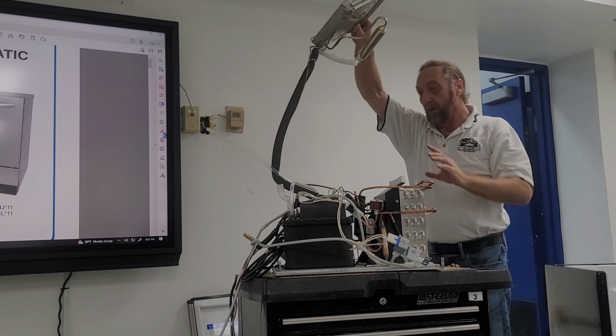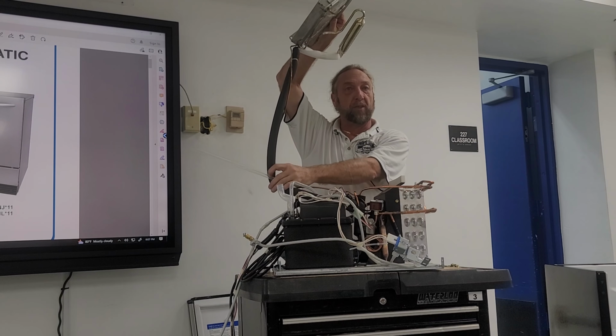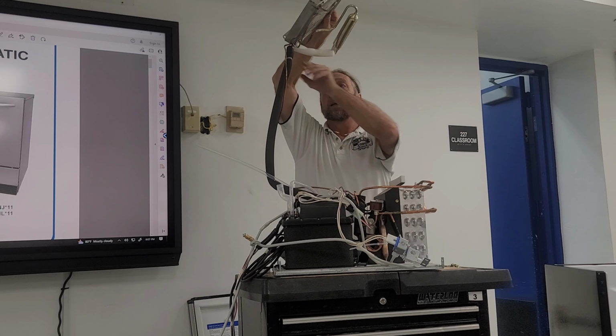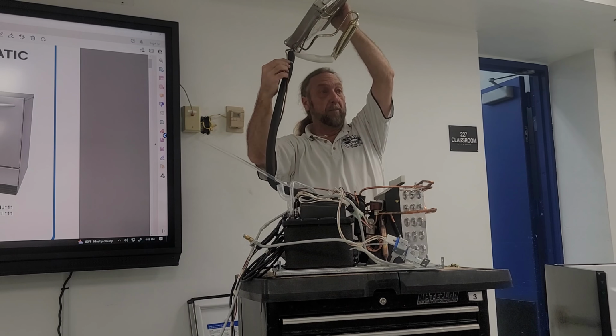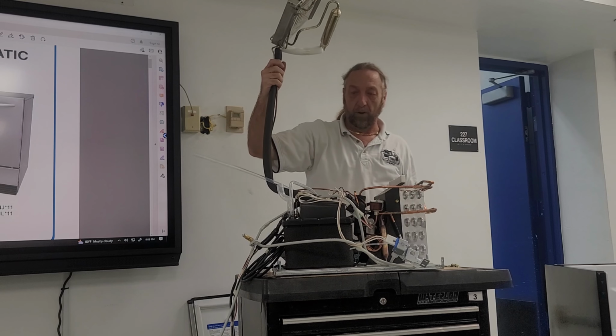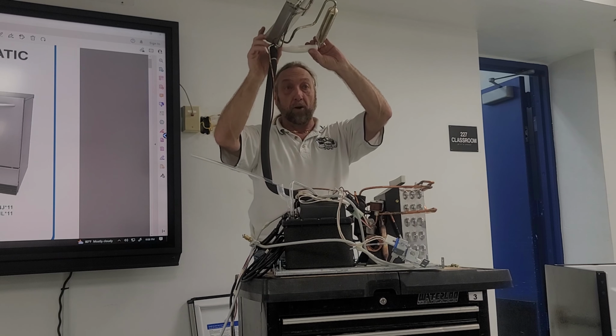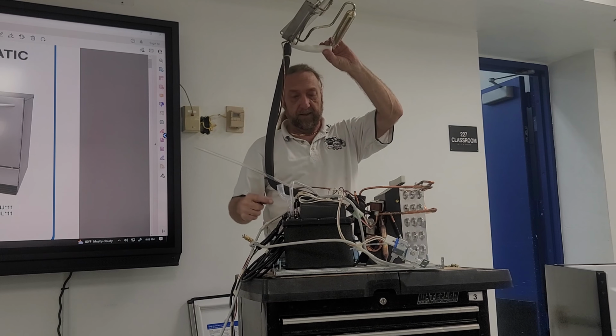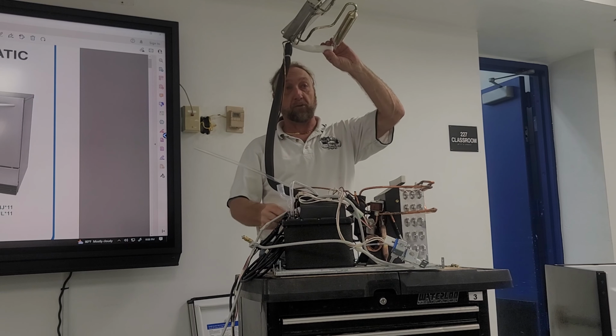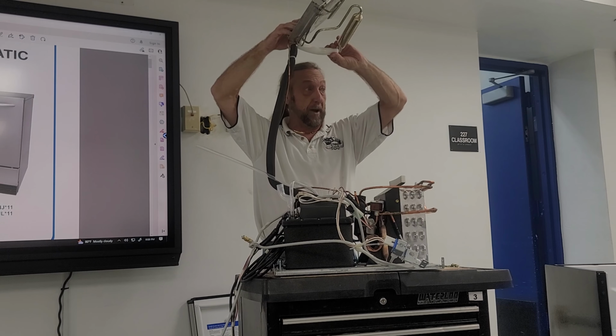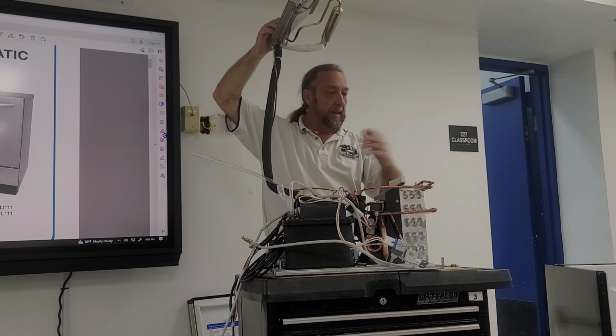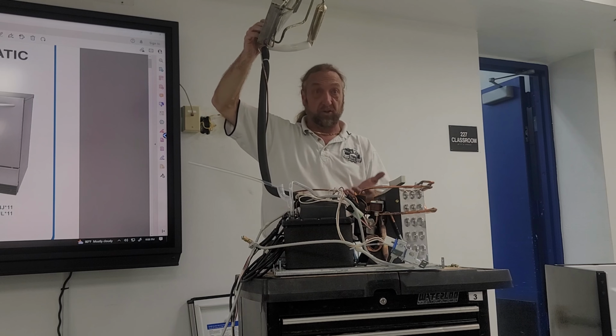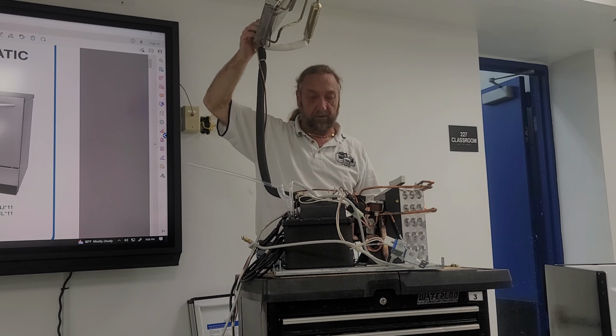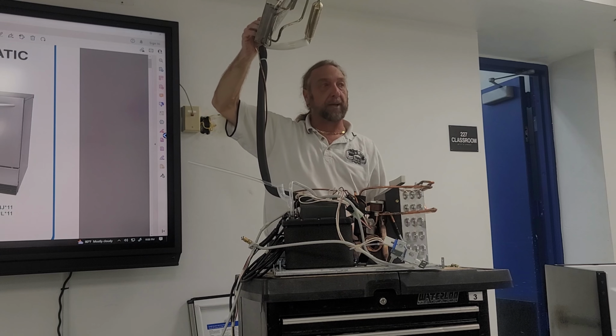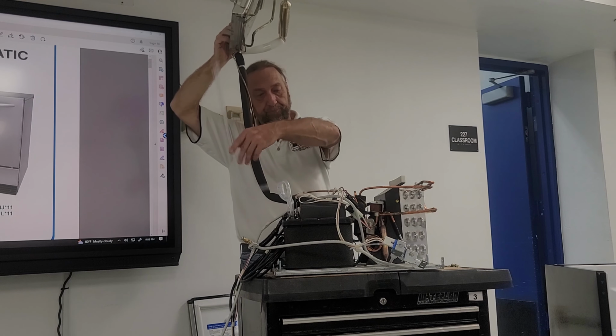So now that we got it open for you to see it, we have to be very careful with this line. I don't want to kink this line here. This line can be easily damaged. We have to be careful. If we're changing the evaporator, it will come with all these lines and connect directly to the compressor. So we just disconnect here and reconnect the evaporator. It's not that big a job. Now that it's open like this, it's easier to service. If I had a compressor to replace, take that whole cover off and I can replace that compressor there.